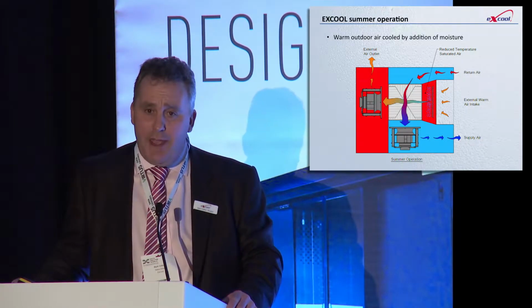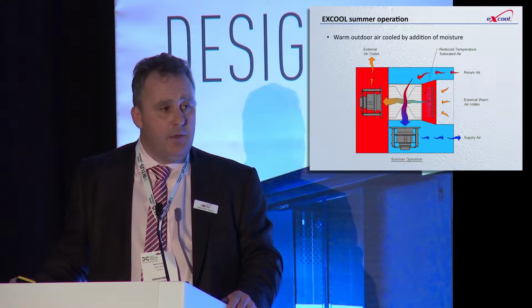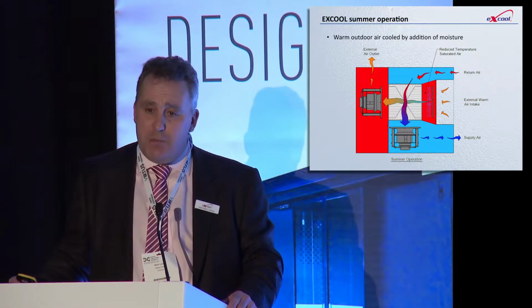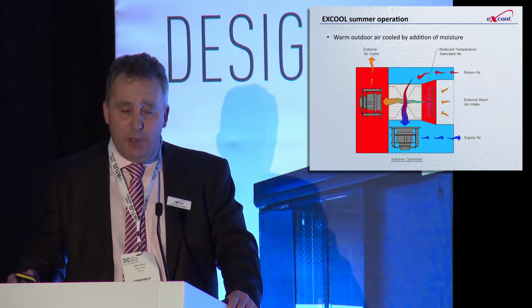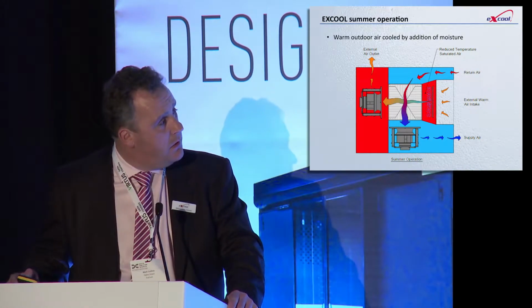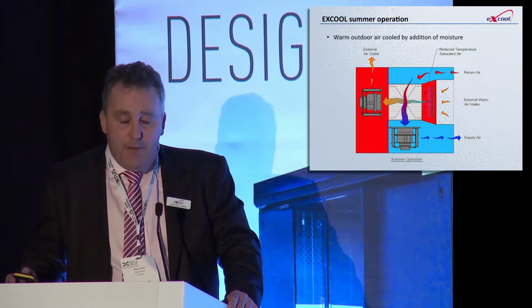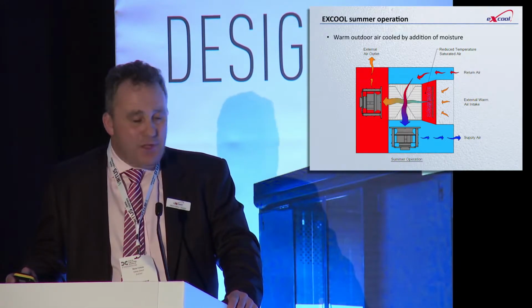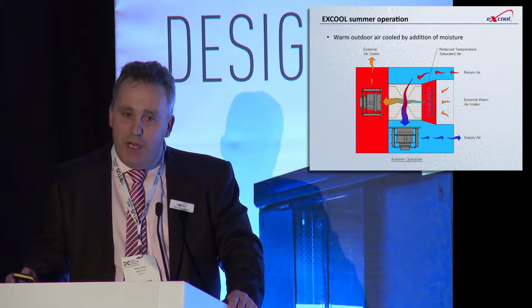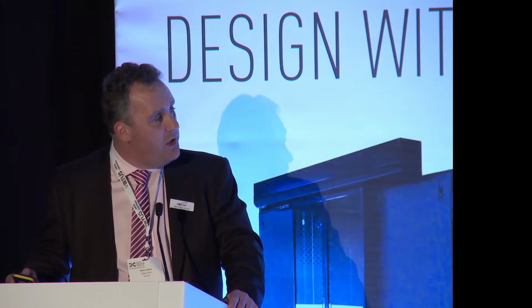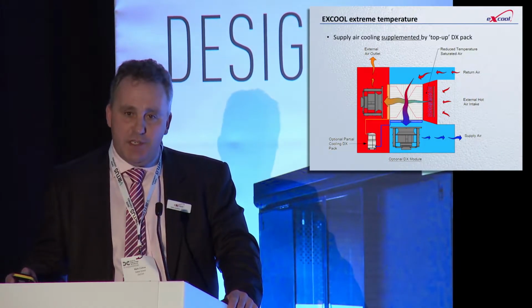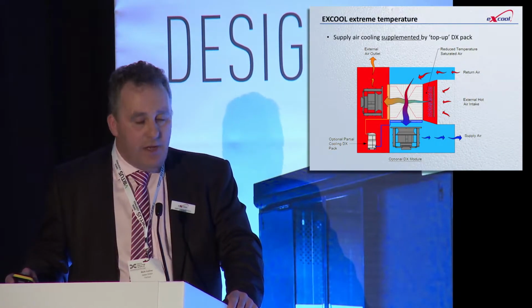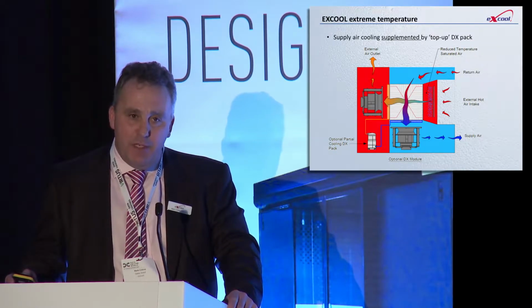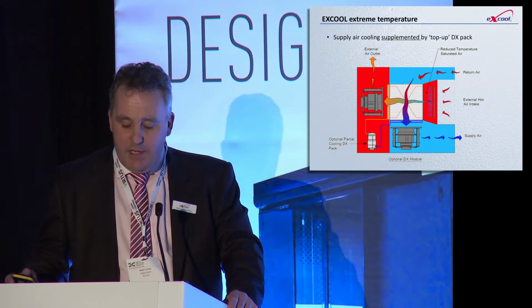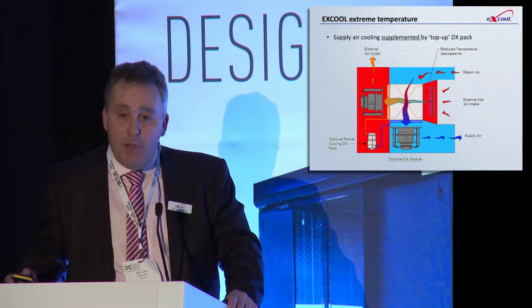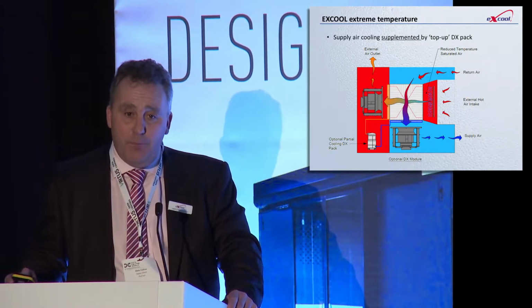That allows us to supply air at 24 degrees C all year round, providing the wet bulb temperature remains at typical UK conditions. In the middle of, let's say, the south of France, or where we have a client that wants a very low supply temperature, we can introduce a top-up DX section. It would normally only be around 25% of the total cooling load, and is there to provide top-up cooling in the middle of summer for a few hours per year.